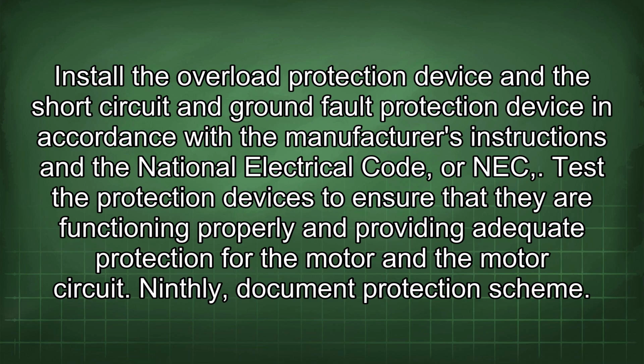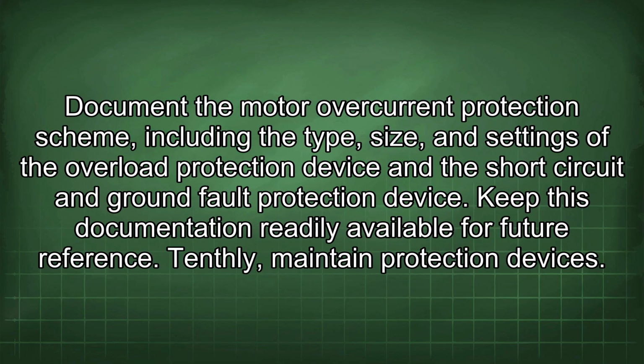Test the protection devices to ensure that they are functioning properly and providing adequate protection for the motor and the motor circuit. Ninthly, document protection scheme. Document the motor overcurrent protection scheme, including the type, size, and settings of the overload protection device and the short circuit and ground fault protection device. Keep this documentation readily available for future reference.